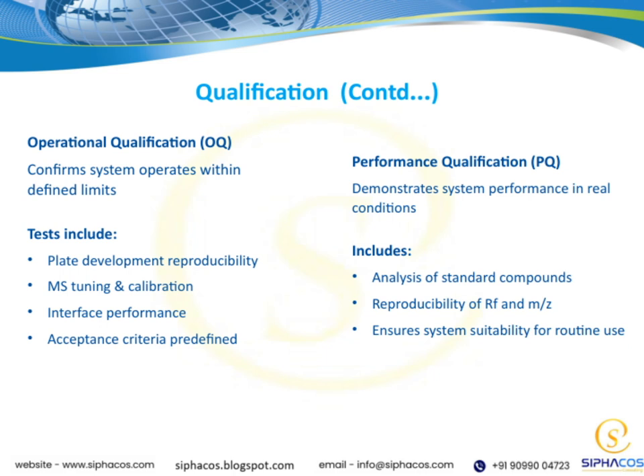Moving on to qualification, which often continues into operational qualification, or OQ. This stage confirms that the system operates within predefined limits. During OQ, we perform specific tests like checking the reproducibility of plate development, tuning and calibrating the mass spectrometer, and assessing interface performance. Each of these tests has acceptance criteria set beforehand, so we know exactly what acceptable performance looks like. By thoroughly qualifying the system, we ensure it's reliable, consistent, and ready for routine analysis, aligning with our overall goal of maintaining high-quality, reproducible data.